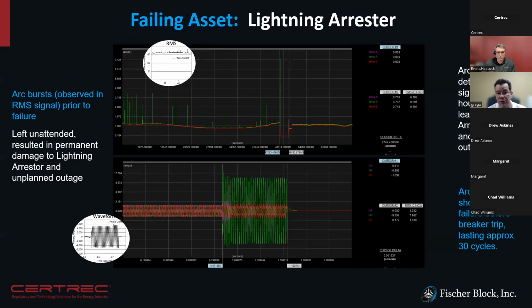And then, lightning arrestor here. So for several hours, days prior to an arrestor failure, we can capture transients, not just at the waveform level, but actually in the RMS. They're severe enough in many cases to manifest, because the RMS signal is typically measured over several cycles. And so transients sometimes can slip through an RMS signal, like in SCADA, a lot of times will not pick up any type of transients, whereas a high resolution waveform monitor would. And so in this case, it was severe enough towards the end where the RMS signal was quite distorted there with those spikes in that signal.